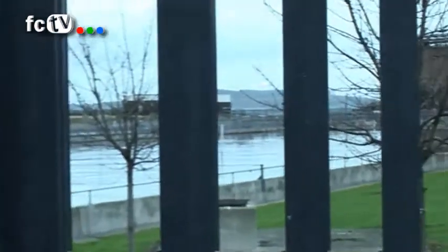Well, if you take the Dublin city, because it's an old city, the sewer system is what we call a combined. The rainwater mixes with the sewage. So in times of heavy rain, you get very large flows coming into the treatment works. If it exceeds a certain figure which says our plant cannot normally handle that, we then have overflow tanks which are on the far side of Pigeon House Road, and they fill up and we store it there. Now, if those tanks, if the weather is of such a nature that even those tanks fill up, it then overflows into the River Liffey, which we're allowed to do in emergency situations.